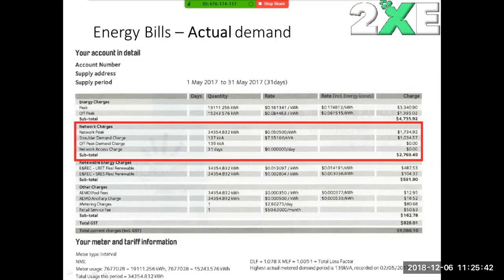You've also got your shoulder demand charges. This value tells you how high your demand was during that shoulder period, the maximum demand during that period. As you can see, it's 137 kVA, charged at $7.55 per kVA, which ends up being about $1,000 a month. You've also got your off-peak demand charges, telling you the maximum demand reached during an off-peak period in kVA, but since it's off-peak, you're not actually getting charged for that demand.